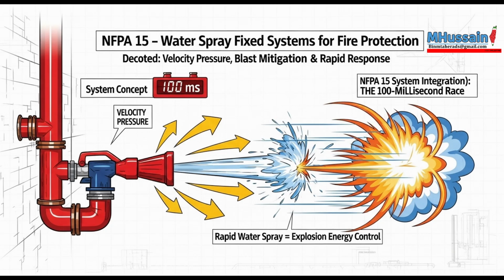So Section 12.3.1.3 mandates that all piping, even the small wet pilot lines that might trigger the system, must be sloped at a minimum of 1 inch per 10 feet toward a drain or vent. 1 inch per 10 feet, minimum. Minimum, and you need air bleeder valves at all high points per 12.3.11.4 to get that air out. If that slope isn't maintained absolutely perfectly during installation or if air gets trapped, the 100 millisecond test will fail, period. That's a level of installation precision far beyond standard sprinkler work.